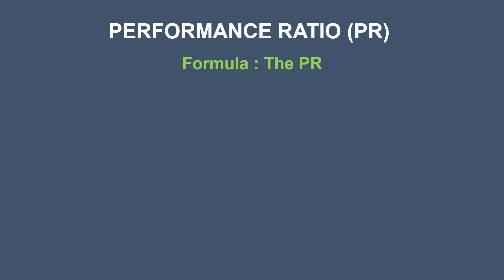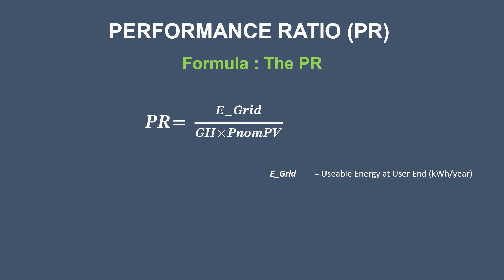Now let's see the formula for PR. PR equals E-grid divided by the product of GII and PNOM-PV. Here, E-grid is the usable energy available at the user end, with units of kWh per year. GII refers to the global inclined irradiation received by the solar PV array at a certain tilt angle. PNOM-PV is the solar PV array's installed DC capacity, with units of kWp (kilowatt peak).